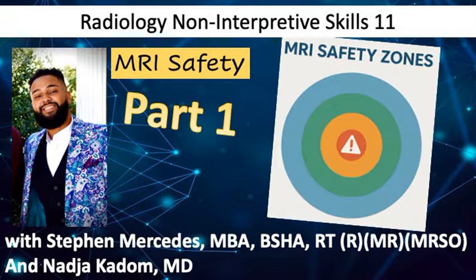So because there are those three different energies, there are three separate categories of risks. When I look at a patient who has an implant, for example, or just someone going into the room, I address each of those concerns through each of those categories. The first is the static magnetic field, which is always on. That is what never turns off. And if it is turned off, it's through the process of the quench, which I'm sure we'll touch on a little bit. But static magnetic field concerns are translational and torque forces. If something is strongly ferromagnetic, meaning it's going to be very much attracted to the magnet, those are the first things that I address. Is it something that's going to be pulled over to the machine? That addresses the static magnetic field.